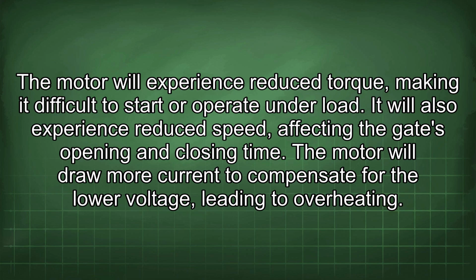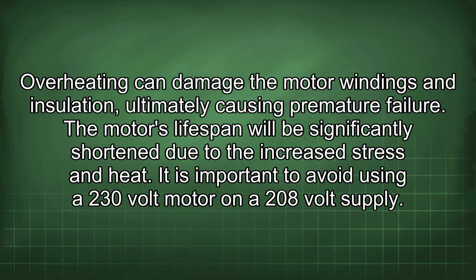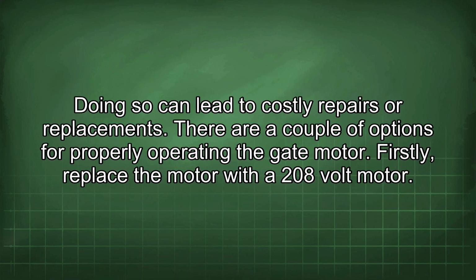The motor will draw more current to compensate for the lower voltage, leading to overheating. Overheating can damage the motor windings and insulation, ultimately causing premature failure. The motor's lifespan will be significantly shortened due to the increased stress and heat. It is important to avoid using a 230-volt motor on a 208-volt supply. Doing so can lead to costly repairs or replacements.